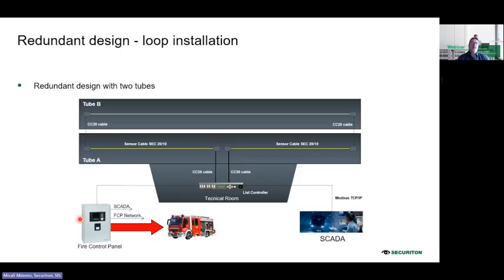Then we have a redundant design called loop installation. Here we have, for example, two tubes, and you can see the linear heat detector cable protecting the tunnel. And when it's coming back, there is one technical room where you can start the installation and come back again on the same controller. This loop installation will help so that in case of an interruption in the sensor cable, you will not lose any communication.